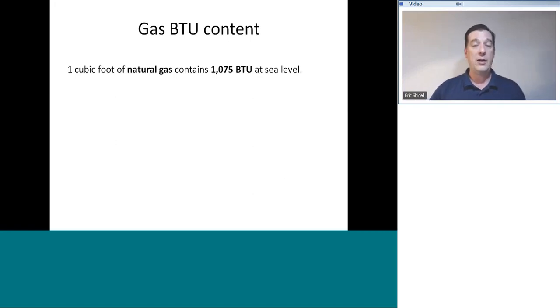And by the way, if you wanted to call up your natural gas provider, which I recommend you do, as a heating and air conditioning technician, you are intimately involved in gas fuels. It's a good idea for you to know what is the heat content of the fuel gas in your market. So call up your natural gas provider and ask them. And what you will ask for is the caloric value. That's C-A-L-O-R-I-C value. Remember, calories are also a measurement of heat. So ask for the caloric value of your gas, and they will give you a number of BTU per cubic foot of their gas supply.